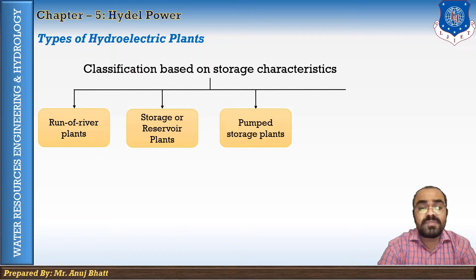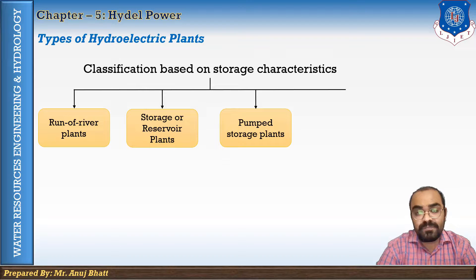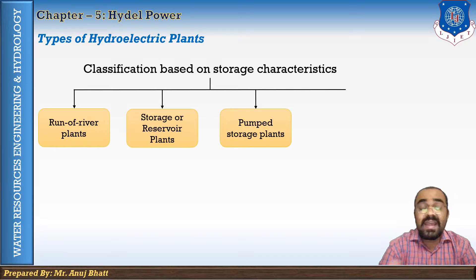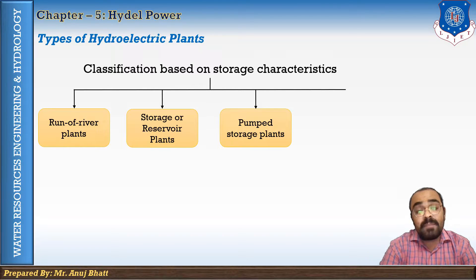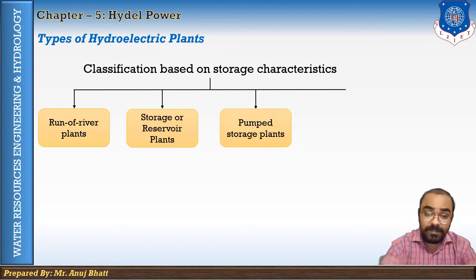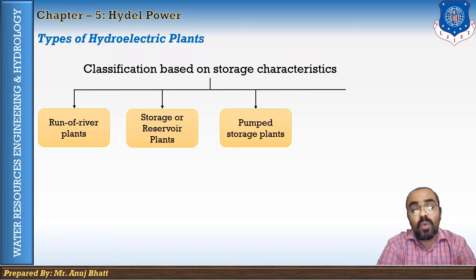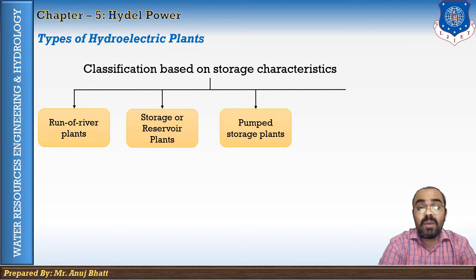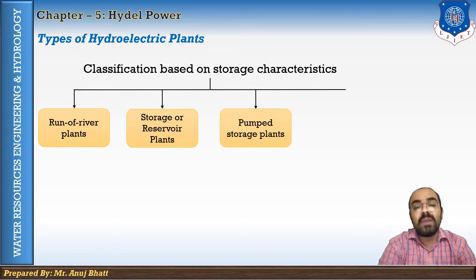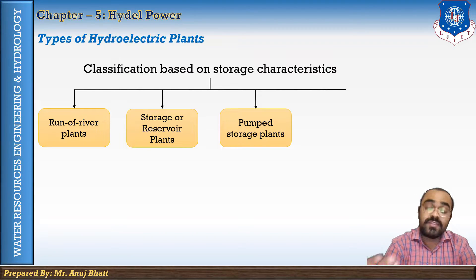The pump storage plant generates power only during the peak load period, while during the off-peak period water is pumped back to the headwater pool. The pumps are usually run with secondary power available from other plants in the system. It is usually not necessary to install a separate pumping system for heads up to 120 meters, as the turbine runners can be used both as a turbine and as a pump.